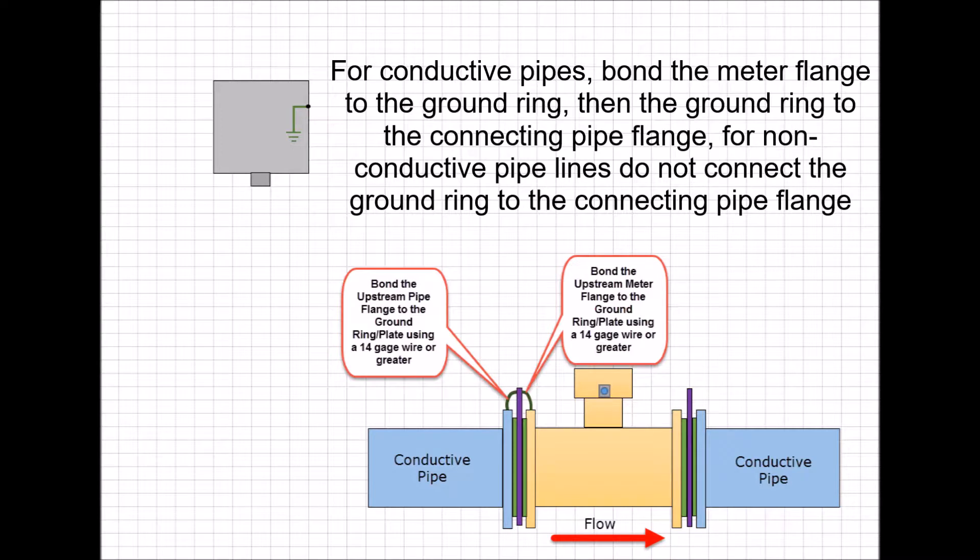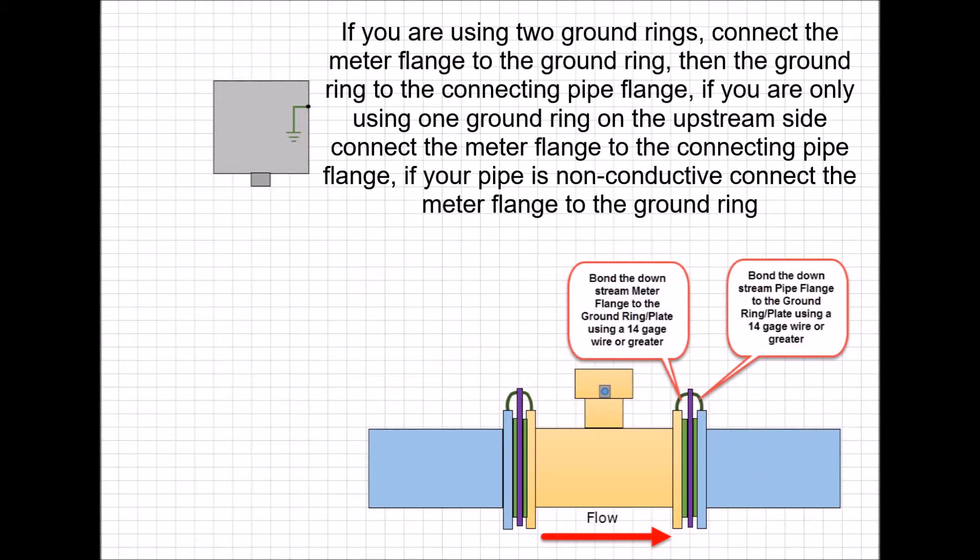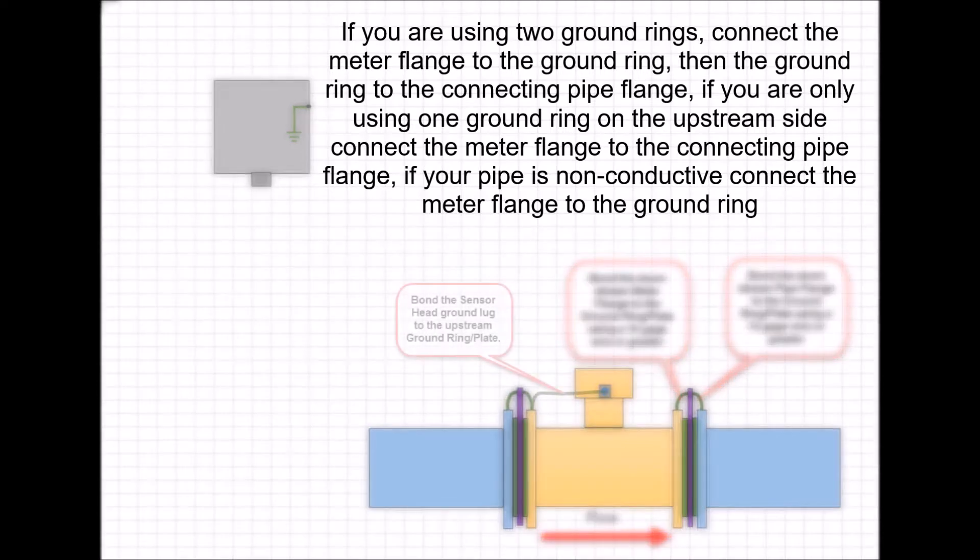For conductive pipes, bond the meter flange to the ground ring, then the ground ring to the connecting pipe flange. For non-conductive pipelines, do not connect the ground ring to the connecting pipe flange. If you are using two ground rings, connect the meter flange to the ground ring, then the ground ring to the connecting pipe flange. If you are only using one ground ring on the upstream side, connect the meter flange to the connecting pipe flange. If your pipe is non-conductive, connect the meter flange to the ground ring.